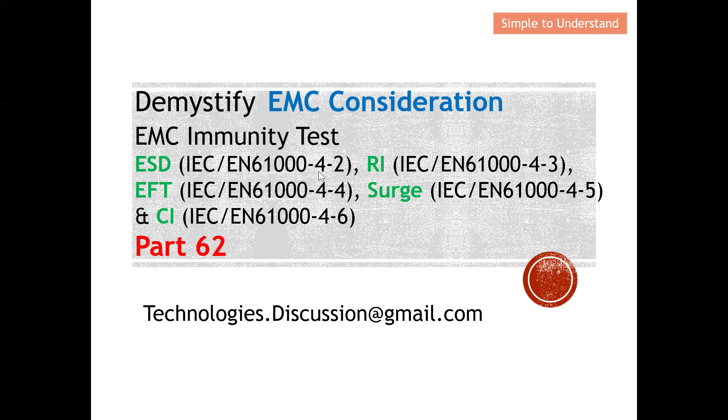You can see that they run in a sequence. For example, this ESD is governed by IEC/EN61000-4-2, radiated immunity is dash 4-3, EFT is dash 4-4, surge is under dash 4-5, and conducted immunity is under the dash 4-6 standard.